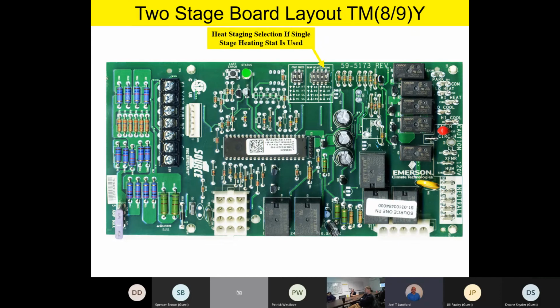The board has got some algorithms in there. It'll start making intelligent decisions on when to stage second stage. So isn't that cool? The board actually becomes a smart staging control if it's in the auto position. And so it's really important that if you have a single stage thermostat, I recommend you put it in the auto position and let the board make some intelligent decisions.